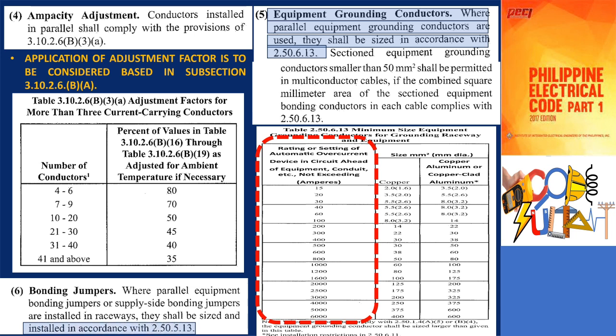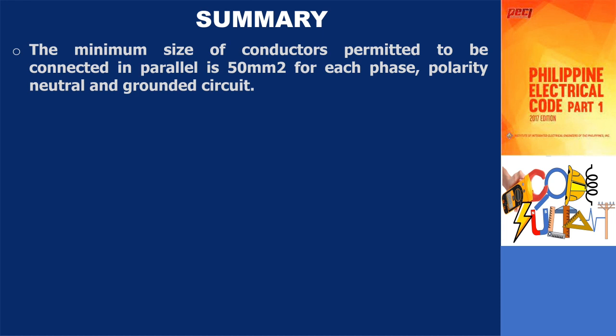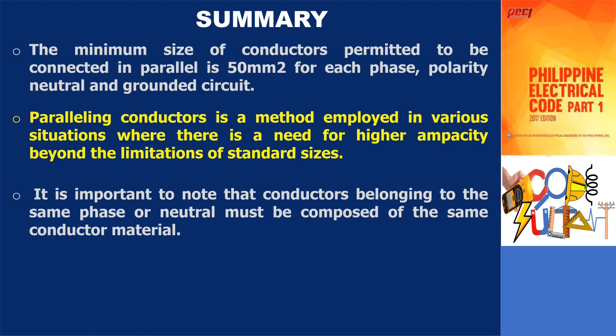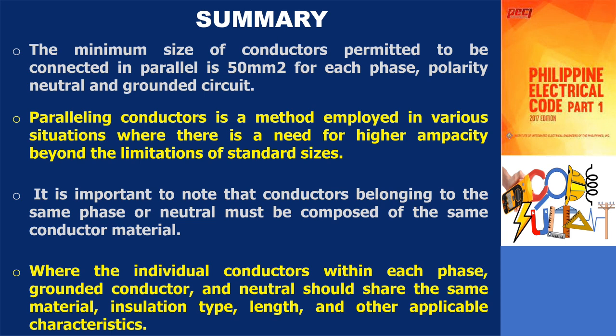In summary, the minimum size of conductors permitted to be connected in parallel is 50 square millimeters for each phase, polarity, neutral, and grounded circuit. Paralleling conductors is a method employed in various situations where there is a need for higher ampacity beyond the limitations of standard sizes. This approach is used when commercially available sizes are not suitable or when the installation process can be simplified by using multiple smaller conductors instead of a single large cable. Additionally, conductors belonging to the same phase or neutral must be made of the same conductor material, ensuring consistency and uniformity, where the individual conductors within each phase, grounded conductor, and neutral should share the same material, insulation type, length, and other applicable characteristics.